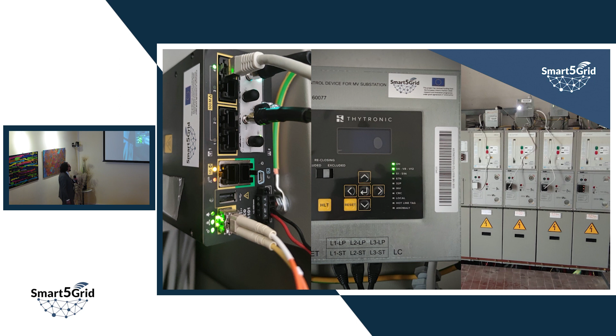To demonstrate that the connectivity was working properly, we performed a real automation test. The picture isn't the best, but we connected the grid through a resistor directly to the ground to simulate a fault. The automation system, as seen in the slide, identified that the fault was exactly at that point, and the grid automatically reconfigured itself to isolate the faulty part. So the field test was successfully executed.